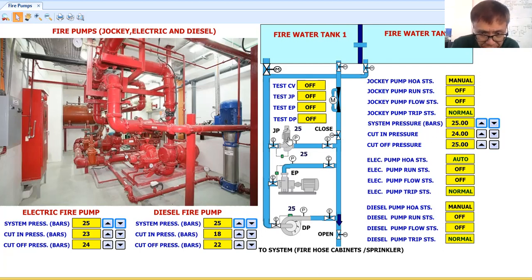First, let us discuss what the use of the jockey pump is. To prevent the fire pumps from running when there is a water leak in the system, we install a jockey pump. The purpose of the jockey pump is to maintain the system pressure. Our system pressure here is 25 bars. So let's say there is a small leak in the piping system. This leak will be addressed by the jockey pump. The 25 bars is the calculated pressure so that the pump can reach the farthest sprinkler in the building. When the pressure drops because of a small leak, the job of the jockey pump is to raise or maintain the 25 bars. So that is the purpose of the jockey pump.